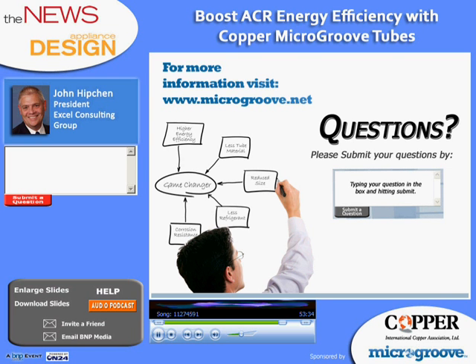Now, this is a related question. Does the refrigerant type alter the MicroGroove design, or is it standard for all types of refrigerants? The MicroGroove design is fairly standard for all refrigerants, but as you would expect, the heat transfer and pressures are going to vary as you go from one refrigerant to another. But you don't see too much change in the type of enhancements in the MicroGroove tubes. Like I mentioned, you're still going to get a superior heat transfer with the MicroGroove tube.